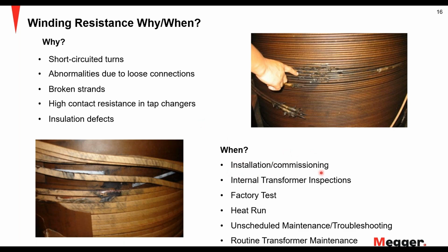When do you do it? It's usually installation commissioning test, internal transformer inspections, factory test, heat run, any kind of routine maintenance or unscheduled maintenance, or you're troubleshooting a transformer, that's when you do this kind of test. It's one of the most common tests that you see in the field, TTR and winding resistance. Those are two kind of bread and butter tests for a transformer to perform routine maintenance.